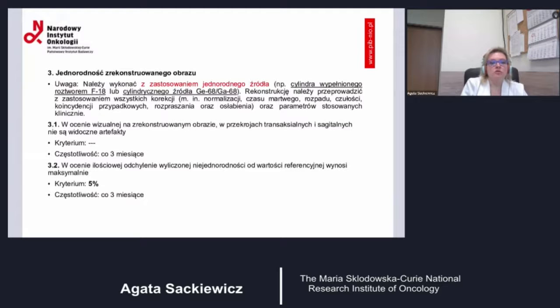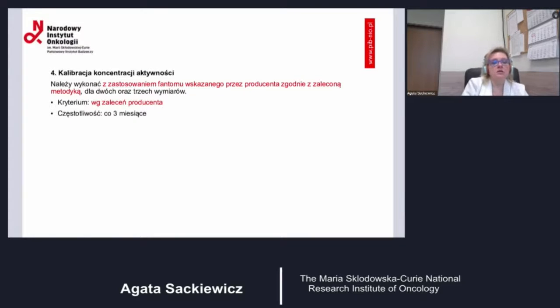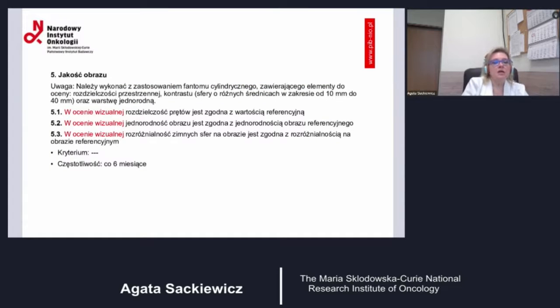When we are looking at the quantitative assessment, we are looking at the deviation of the computed heterogeneity from the reference value. Here the criterion is a maximum of 5% and the frequency is every 3 months. And the fourth type of test is the calibration of the activity concentration. It should be performed using a phantom recommended by the manufacturer. Frequency of performance of this test should be scheduled every 3 months.